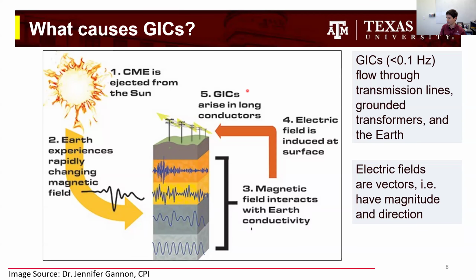Let me back up a second. First, the changing magnetic field interacts with the deep Earth conductivity, which has a lot of uncertainty in its models - that's the subject of ongoing work at USGS. This causes an induced electric field at the surface, which normally we wouldn't care about, because something like 3, 4, 8, or 12 volts per kilometer isn't normally a problem - unless you have a 200-300 mile or kilometer-long transmission line, which could then have a potential difference between bus and bus of say 3,000 volts, for a bad case.